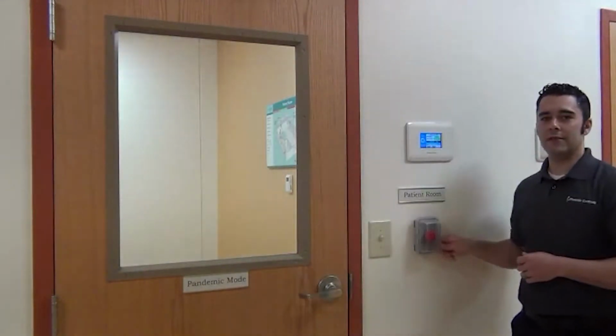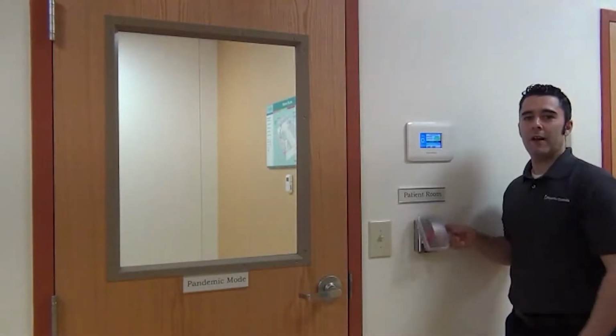have something similar to this. And again, this is a little bit dramatic to have this big button on the wall, but you can have a key switch, or you can have a button, or you can have a BMS writable command to trigger a pandemic mode inside of the space. Now, what happened when I just pushed that button is the supply valve is going to increase the air change rate in that room. The return valve is going to go into its shutoff position, and the general exhaust valve is going to open. So I increased the ventilation rate, I made the room negative, and I changed from 100% return air to 100% exhaust air without having to do anything other than flip a switch or send the BMS command to turn on pandemic mode.